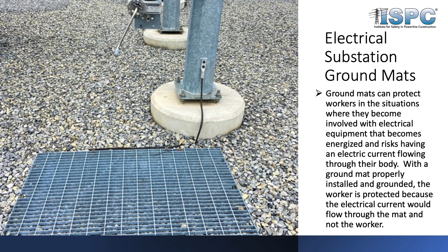So it's very important to make sure these connections are intact when working inside a substation. Here you see a picture of a ground mat. We use these not only in the subs but out in the T&D world as well. This is at the base of a gang-operated disconnect — you can see the handle at the top of the picture, operating the disconnect at the top of the structure. You can see a ground tail to the structure also connected to the ground mat and to the substation ground grid. These mats are placed wherever you may be operating equipment that could potentially become energized if something goes wrong.